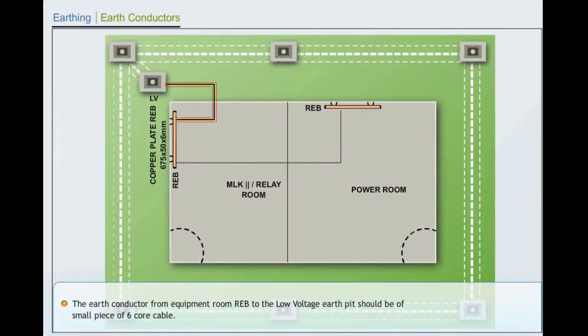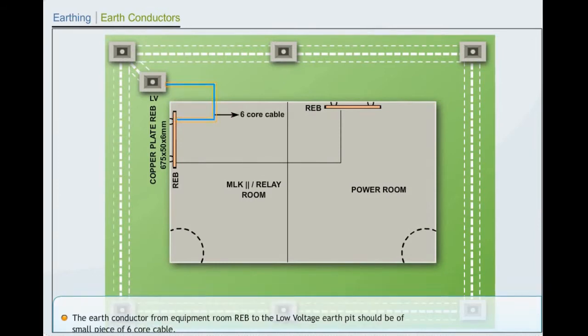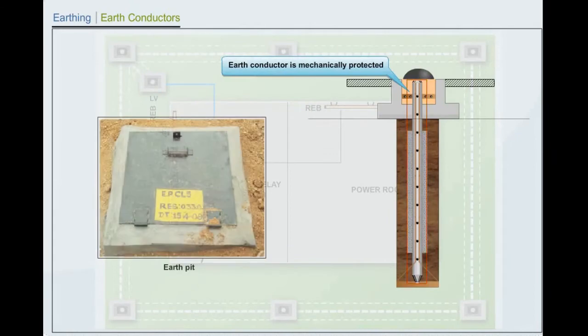The earth conductor from equipment room earth bar to the low voltage earth pit should be of small piece of 6-core cable. As the earth conductor is buried in the ground, it is protected mechanically. For diversity, it is proposed that there shall be 2 such earth conductors up to the first low voltage earth pit and then on to the nearest building perimeter earth pit.